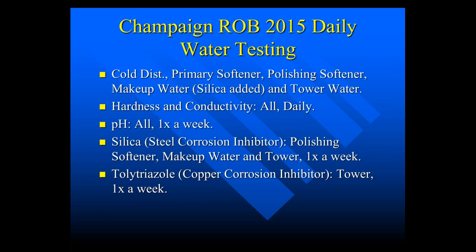Daily, we tested the cold distribution, the primary softener, the polishing softener, and then the makeup line where silica was added, and the tower water. We measured hardness and conductivity on all those samples daily, pH once a week, silica (the steel corrosion inhibitor) on the polishing softener, makeup water, and tower once a week, and tolytriazole on the tower once a week.